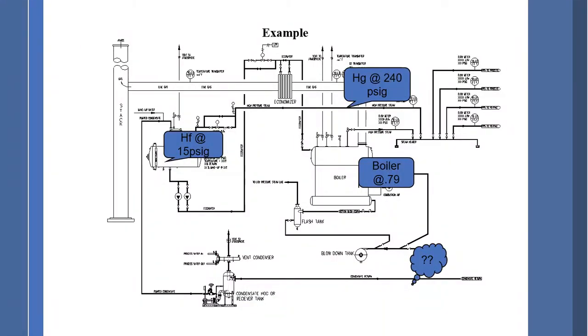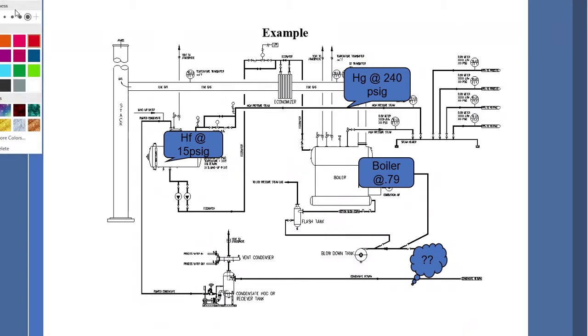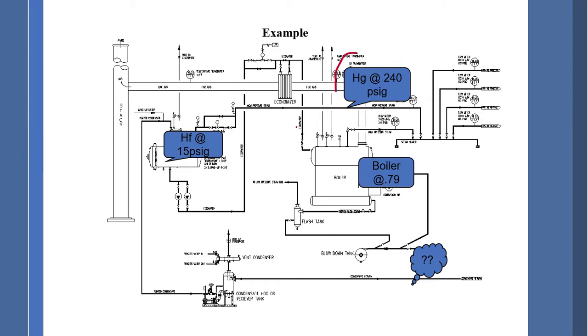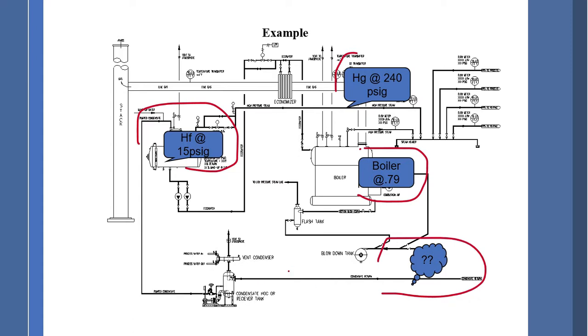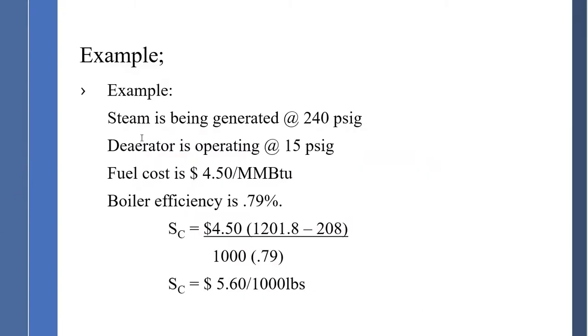As an example, we're going to use a boiler operating at 240 PSI. Our deaerator is operating at 15 PSI and our boiler efficiency is at 0.79 — though there's always the unknown of what condensate is being recovered. Fuel cost is $4.50 per million BTUs. So our calculation uses 1201.8 BTU/lb — the enthalpy of steam leaving the boiler — and 208 BTU/lb — the sensible energy of the feed water going into the boiler — divided by 1000 divided by 0.79. We come up with a fuel cost of $5.60.